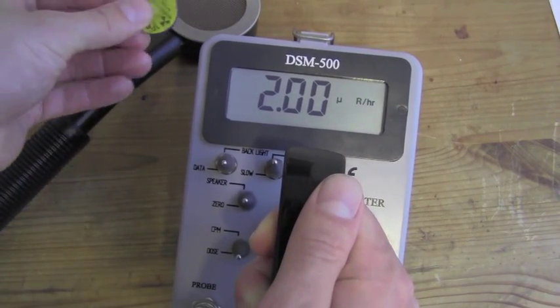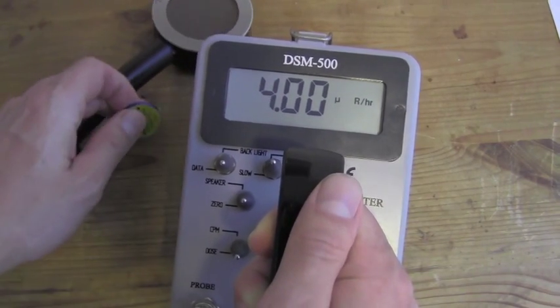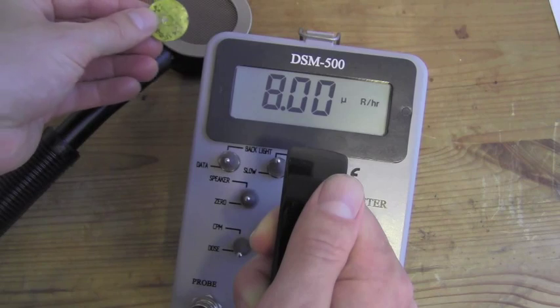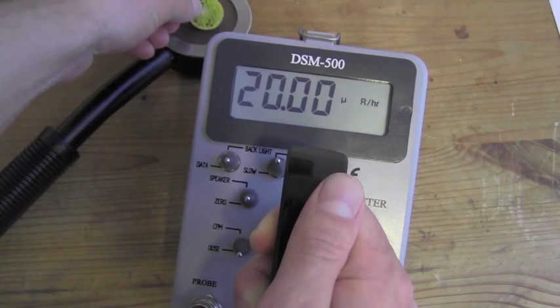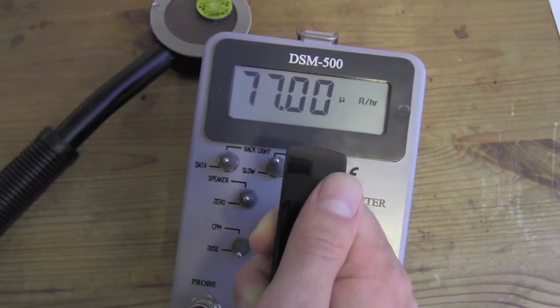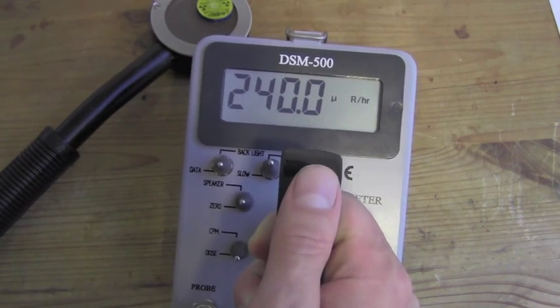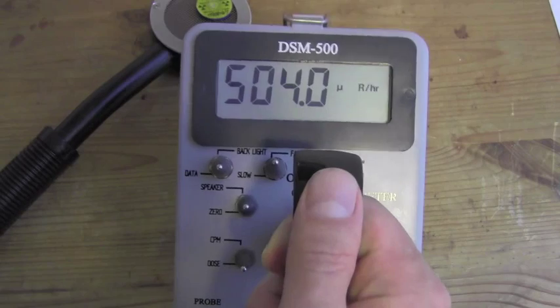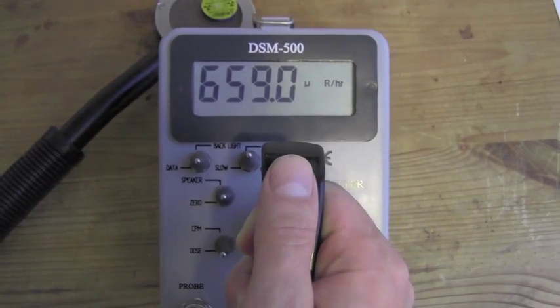I am going to place the source on top of the window on the pancake GM probe. You see we have a nice response in micro-R per hour.